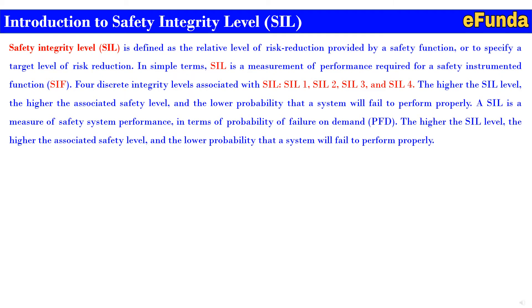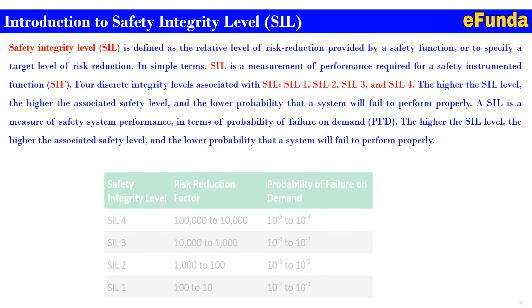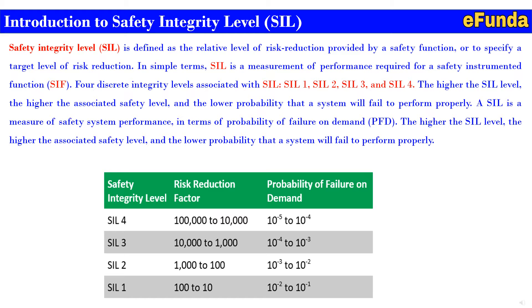Starting our today's video with an introduction to Safety Integrity Level, that is SIL. Safety Integrity Level is defined as the relative level of risk reduction provided by a safety function, or used to specify a target level of risk reduction. In simple words, SIL is a measurement of the performance required for a Safety Instrumented Function, that is SIF. Four discrete integrity levels are associated with SIL: SIL 1, SIL 2, SIL 3, and SIL 4.